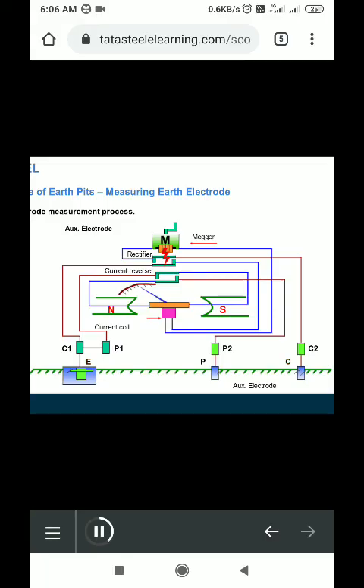This causes flow of current through the soil into the current coil of the earth testing megger. Now the voltage is measured across the E and P terminals by the potential coil. The torque developed is proportional to V by I, which in turn gives the value of earth or soil resistance, and the current is passing through the soil. Depending on the soil resistivity, the megger senses the amount of current passing through the devices in terms of how much voltage is applied and how much current is going through the soil.